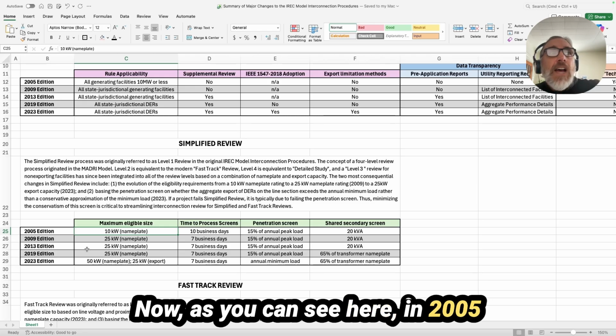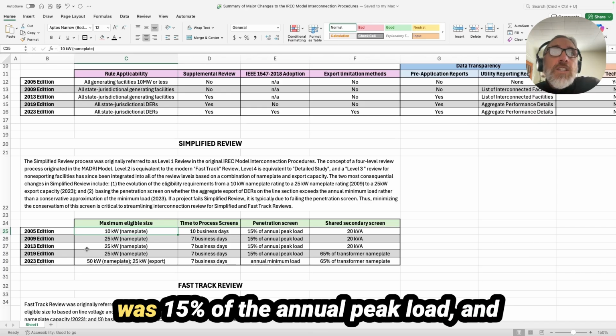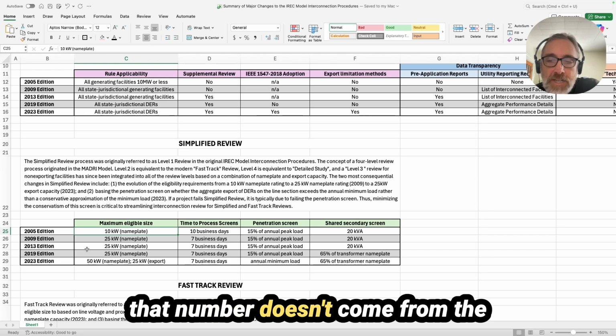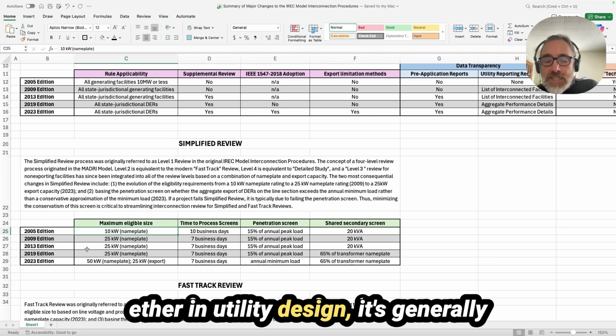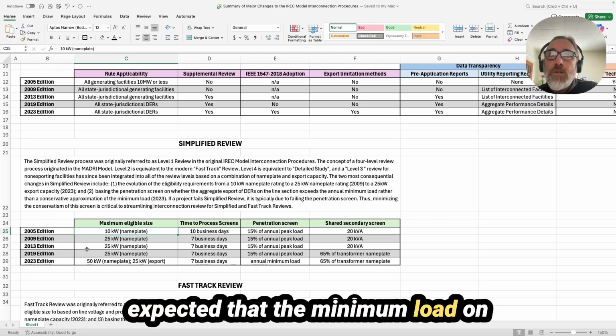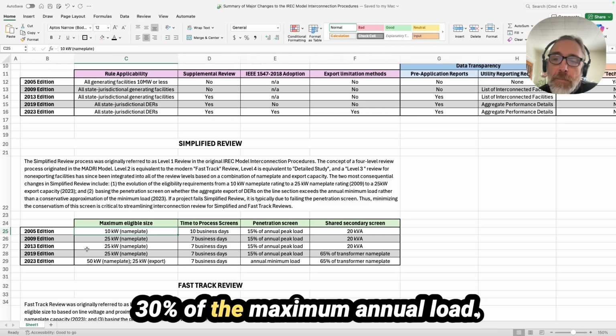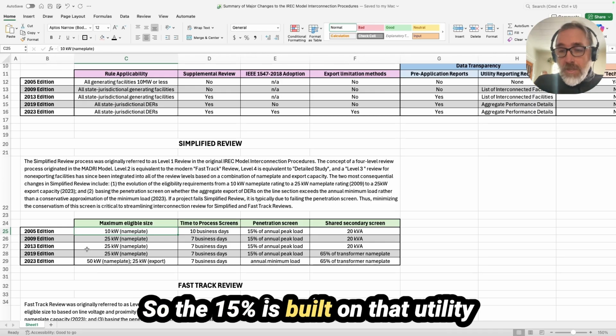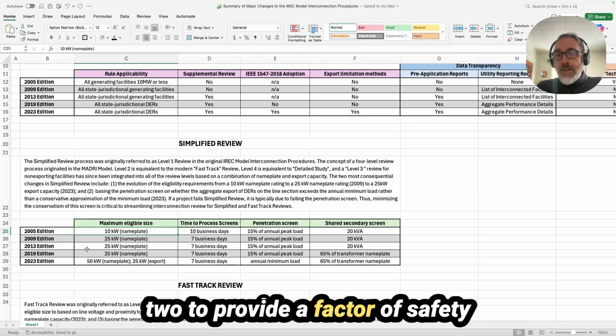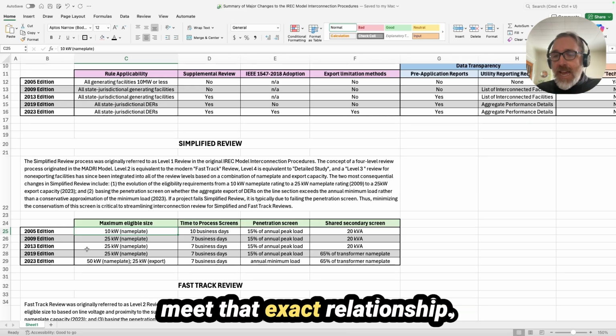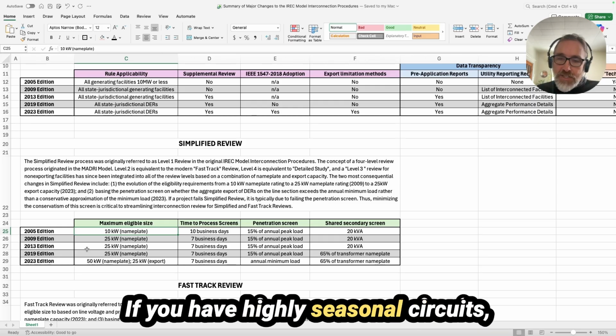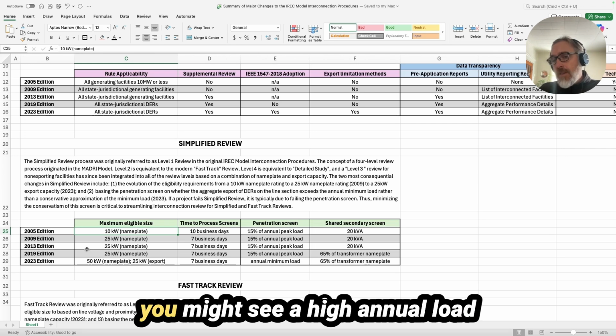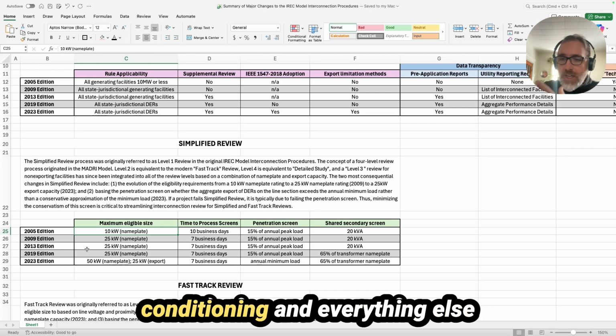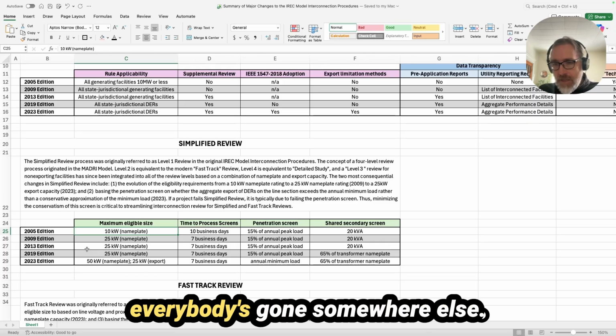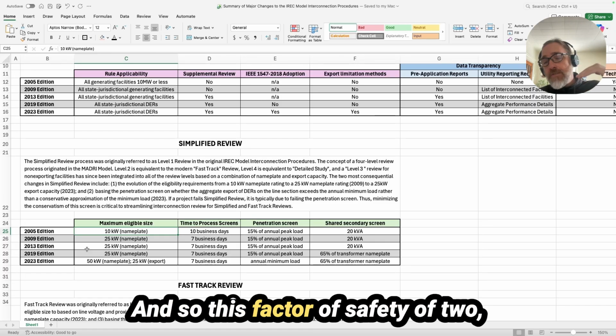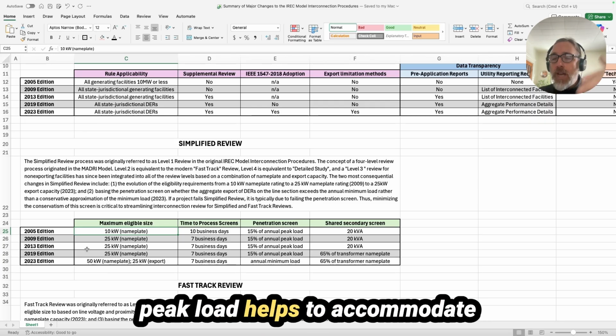Now, as you can see here in 2005 through 2019, that penetration screen was 15% of the annual peak load. And that number doesn't come from the ether. In utility design, it's generally expected that the minimum load on a circuit is going to be approximately 30% of the maximum annual load. So the 15% is built on that utility standard, and it's just divided by 2 to provide a factor of safety of 2 for circuits that may not meet that exact relationship. If you have highly seasonal circuits, let's say in a summer resort town, you might see a high annual load in the middle of the summer for air conditioning and everything else that's going on in that community. But then in the wintertime, everybody's gone somewhere else. That 30% may not hold true. And so this factor of safety of 2, which created this 15% of annual peak load, helps accommodate those types of scenarios.